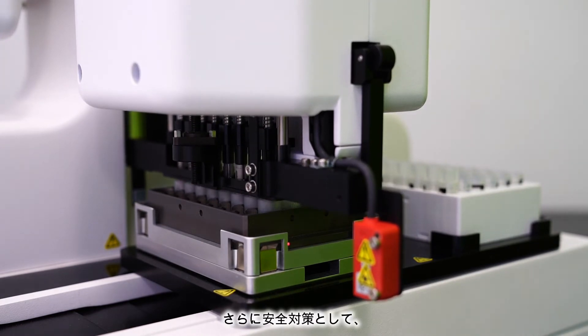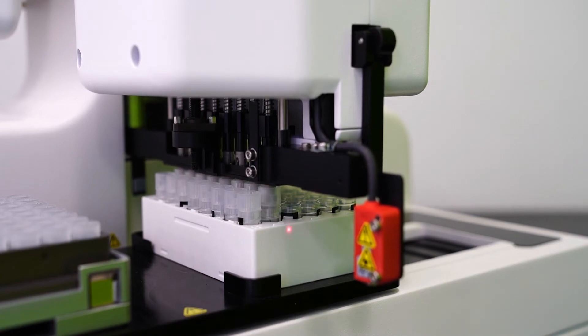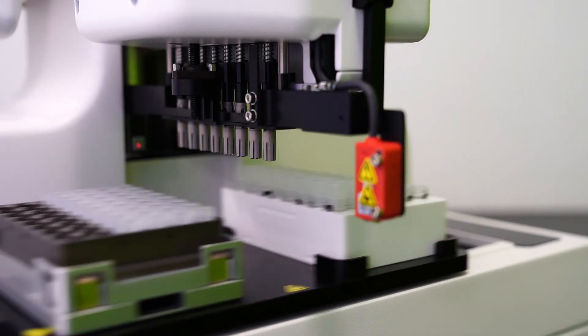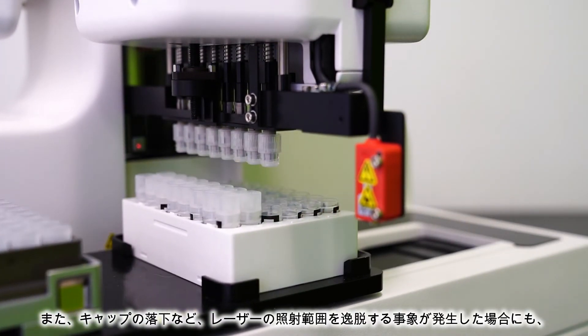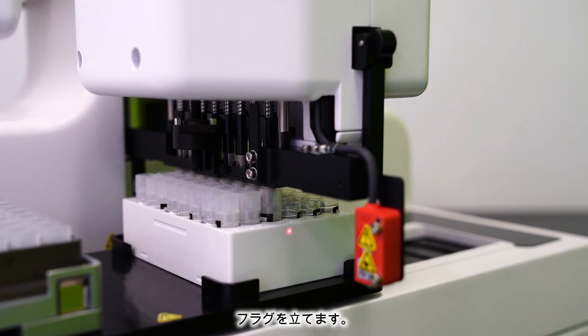As an additional safety measure, a built-in laser constantly monitors the process to error- and collision-proof the entire system. For example, if the wrong labware is present, the laser will sense the incorrect tube height and flag the error. If any other issue occurs which breaks the field of the laser, such as a dropped cap, that will also be flagged.